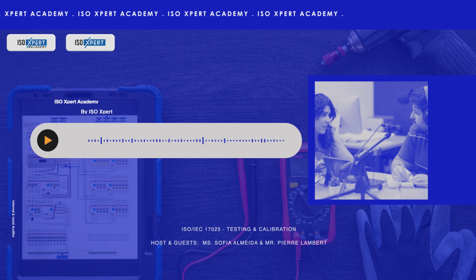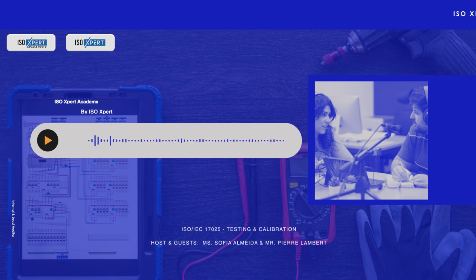Auditors check the lab's policy on record management. How long are records kept? How are they protected from damage or loss? Can they be easily retrieved when needed? This ensures traceability and accountability over the long term. Okay, now this next one sounds really proactive. 8.5, actions to address risks and opportunities.